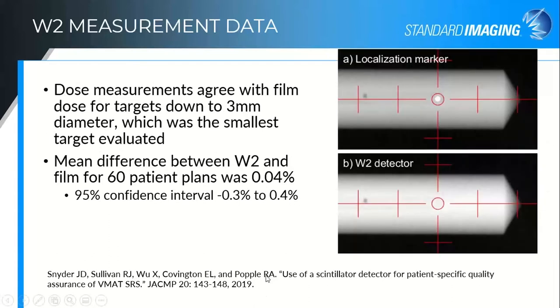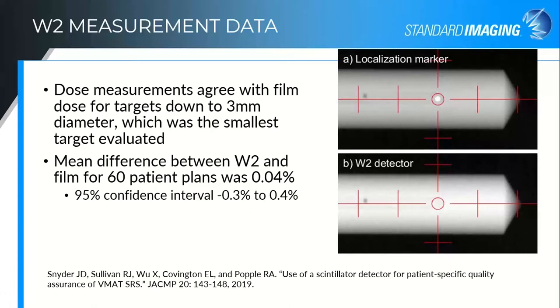Another publication from Richard Popple's group at the University of Alabama at Birmingham looked at patient target measurements to see how small a target they could measure accurately with the W2 comparing it with film. They looked at targets down to a three millimeter diameter and got excellent agreement between the film and the W2, and actually lower variation between measurements — lower uncertainty with the W2 compared with film. The images shown also indicate water equivalence — you can't see where the W2 scintillator is within the chamber plug. We do provide a BB marker fiber, a dummy fiber, so you can localize it with your imaging system and make sure you're aligned properly before treating your phantom plan or doing small field measurements.